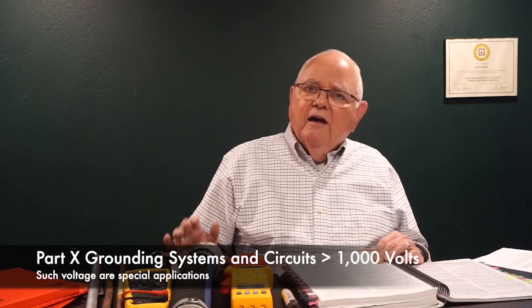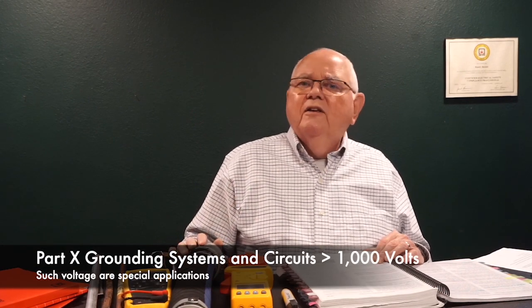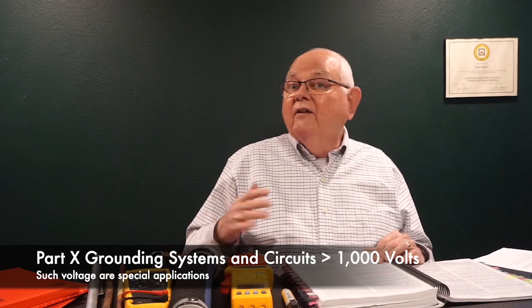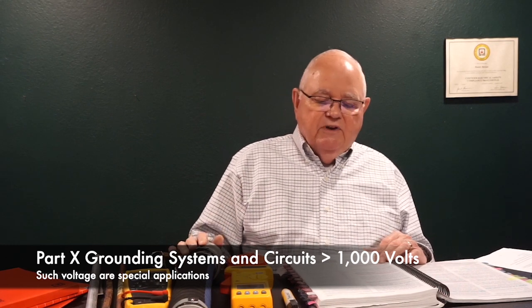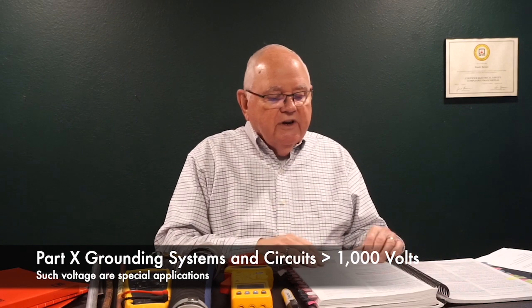And then I know a lot of you get involved in systems over 1,000 volts. A lot of medium voltage systems, high voltage systems out there. And how do I ground those? It's a little bit different. I can have a multi-grounded neutral system where I don't ground my neutral just at one point. I may ground it at different points along the neutral. So that's covered in part 10. If you're familiar with, we have solidly grounded neutral systems and we may have reactance grounds and things like that, impedance grounds. So all covered in part 10 then. Of the NEC. So that is how the NEC is divided up then.